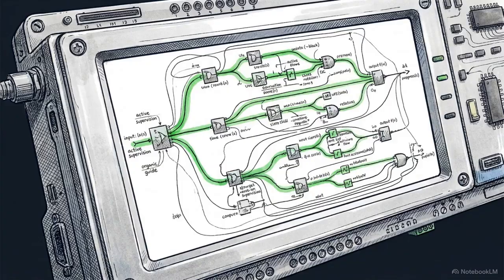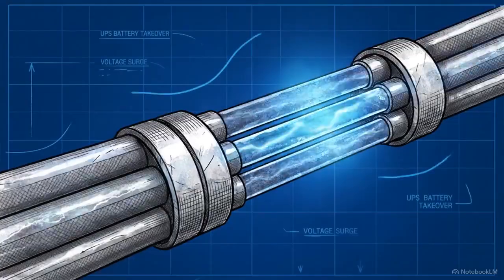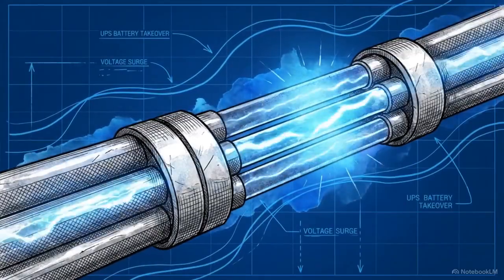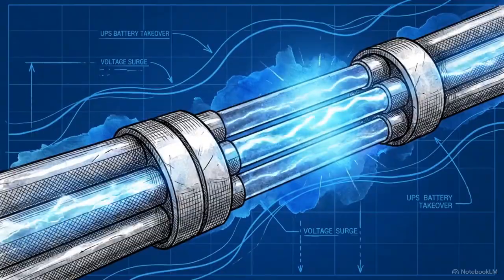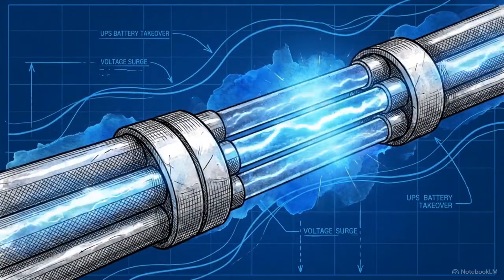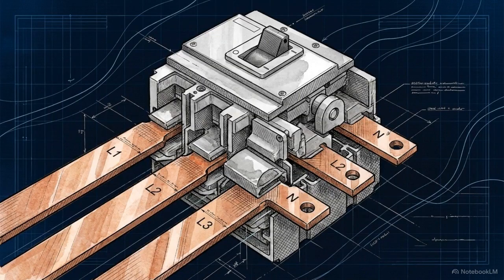In this state, the controller actively supervises the grid and uses source priority logic to respond to unexpected failures mechanically and immediately. If the primary grid fails at time 0, the UPS detects the drop in milliseconds and instantly shifts the load to internal battery power. But this creates a hidden electrical hazard.